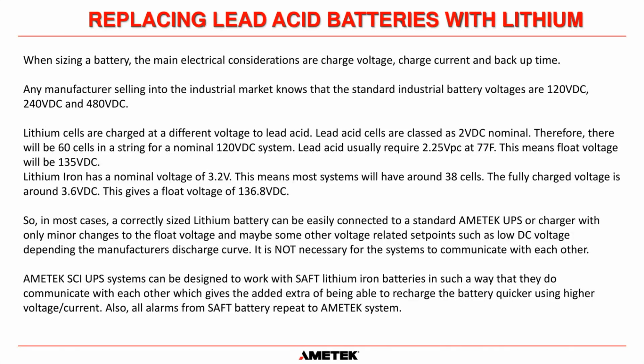And my point is, it is not necessary for the systems to communicate with each other. There doesn't need to be any kind of Ethernet connection, or the systems don't need to talk to each other. A lead acid battery does not talk to the UPS, and a lithium battery does not need to talk to a UPS. Now, there are some benefits of a lithium battery BMS system talking to the charger that is charging it.